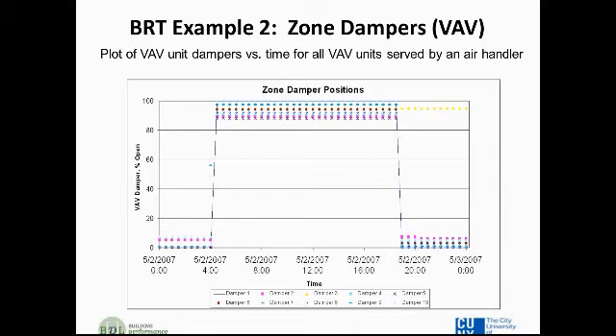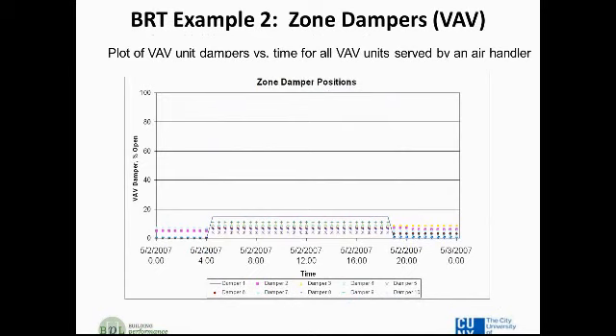We like the VAV dampers to be around that area. It's a good area for them to be in terms of overall control of the system. Here's another example of that same scenario. Only in this case, we see that the dampers are yawning wide open, and you can see that there's even one damper, it looks like damper number 3, open all into the night on that first night. When they're open this wide, it means that they're asking for more air. They need more air. They are, as we say, starved. And so in this case, if you've got the ability to build the trend chart for these kinds of zone damper positions, you can see that you've got some real issues here and that your system obviously needs some more air. Let's go on to this next example.